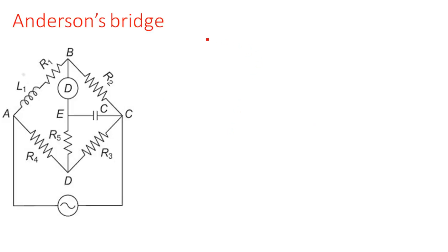Hi everyone, in this video I am going to explain about Anderson bridge. Anderson bridge is also used to measure the unknown inductance like your Maxwell's bridge and Hay's bridge. But here the Anderson bridge measures the inductance ranging from microhenry to several henries.